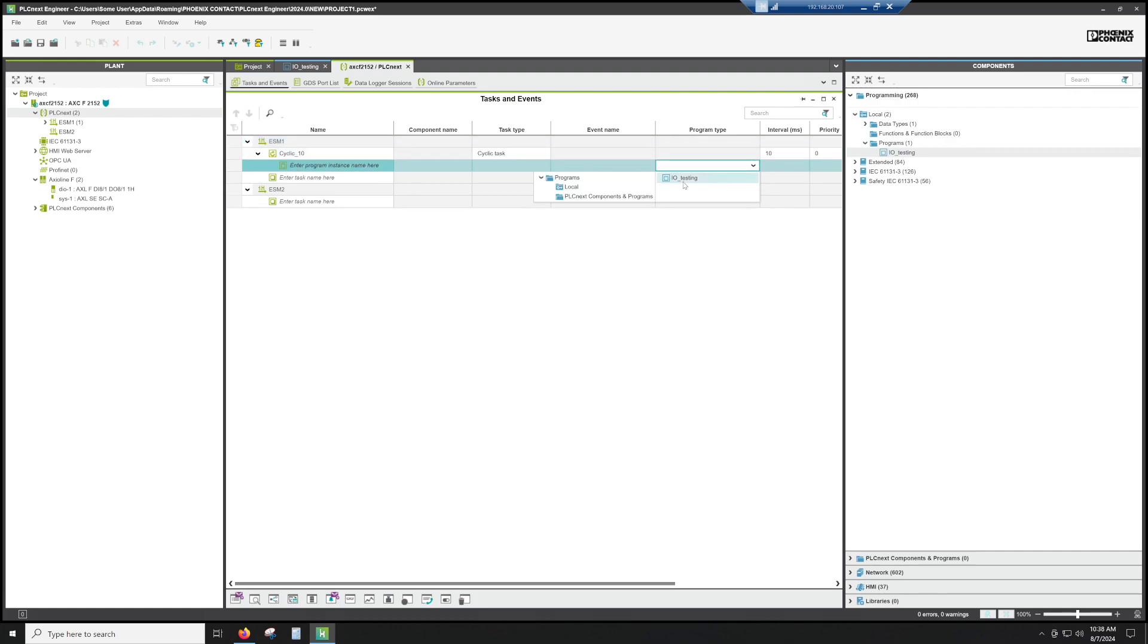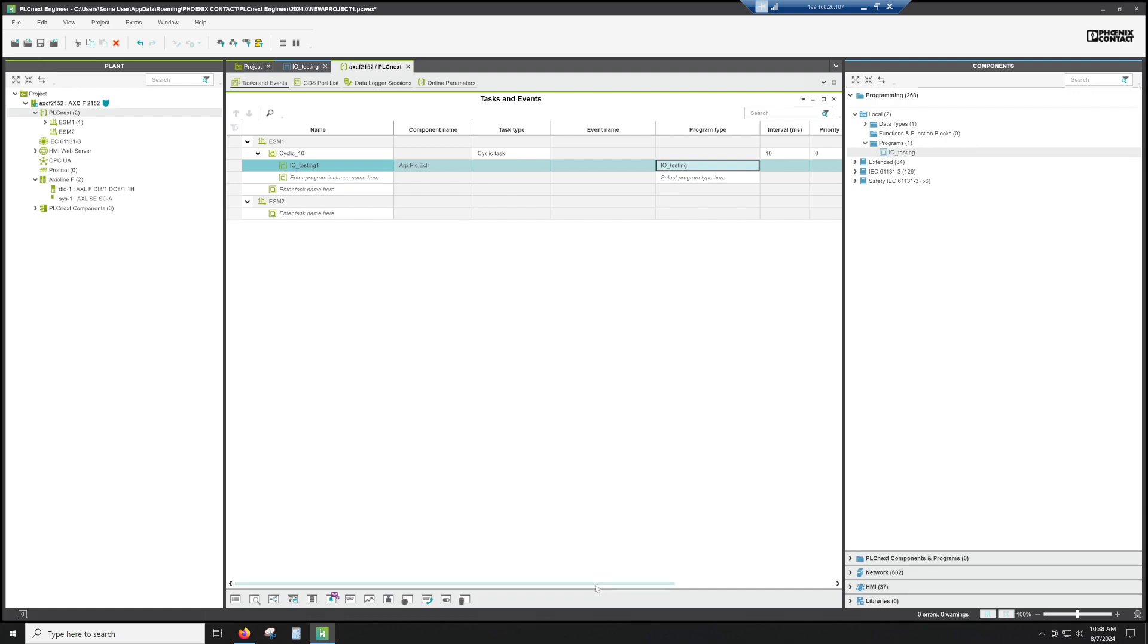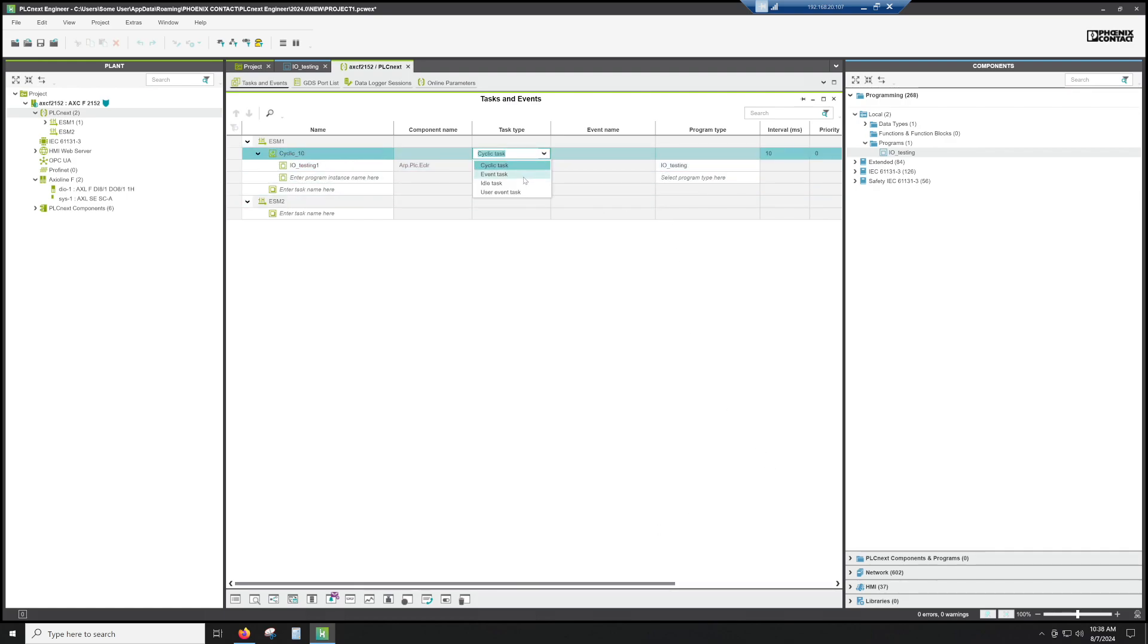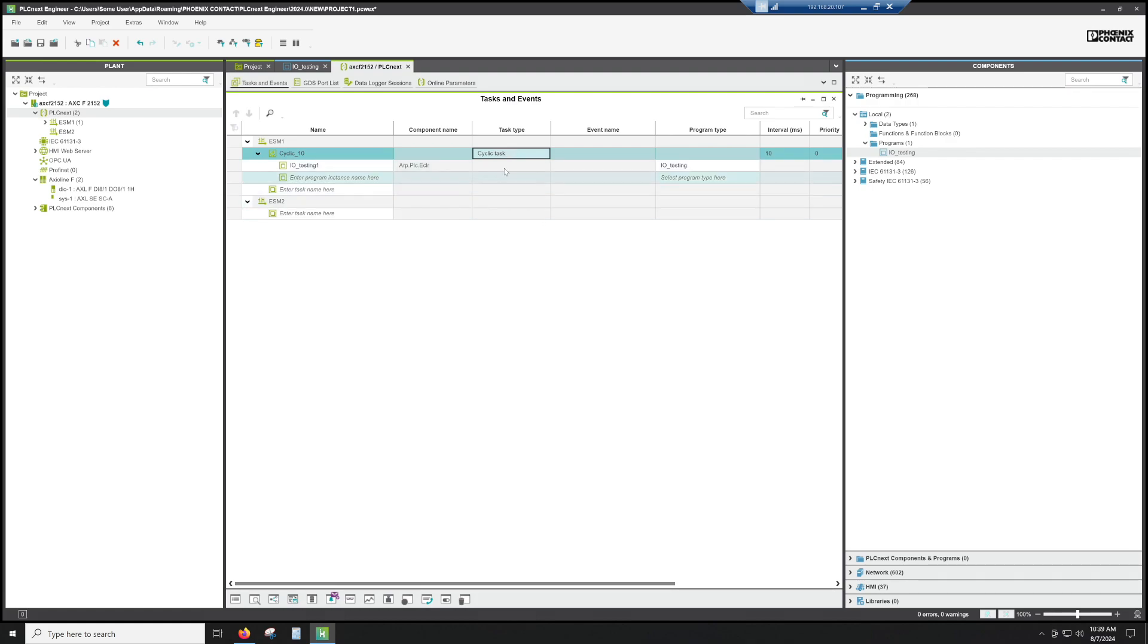So if we take the program and we put IO testing, now that IO testing program will be running every 10 milliseconds, basically on a timer. Like I said, the other options are event task, idle task, and user event task. I usually stick in cyclic and idle task, but I actually prefer cyclic cause I can build my own timers based on a 10 millisecond interval and some other things. So that's all you need to do.